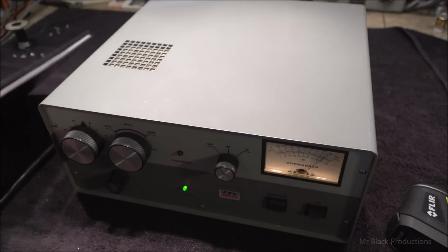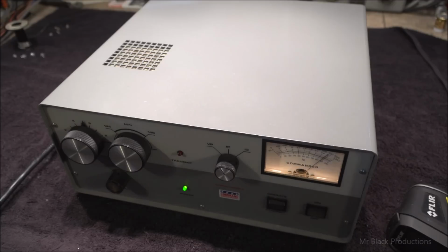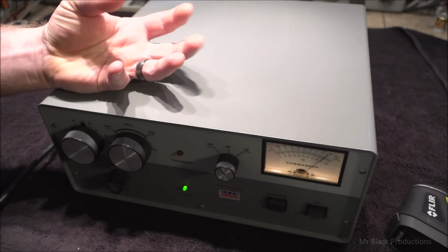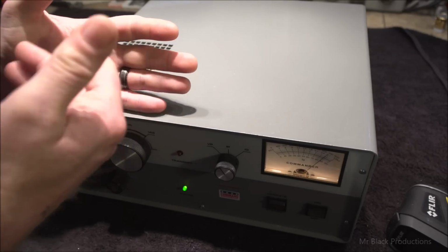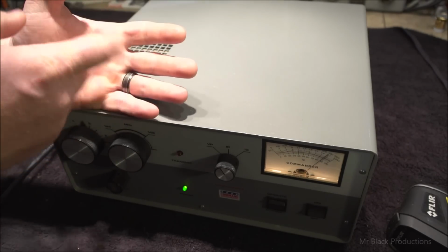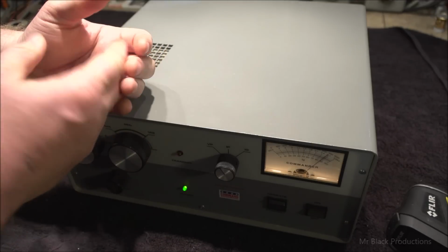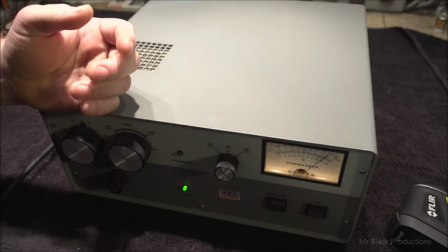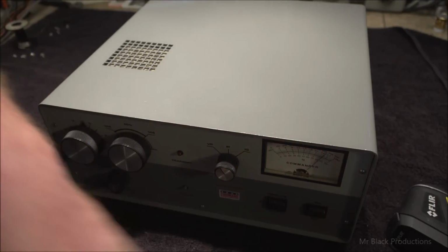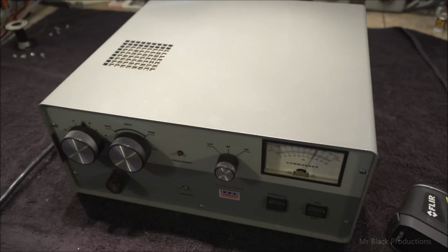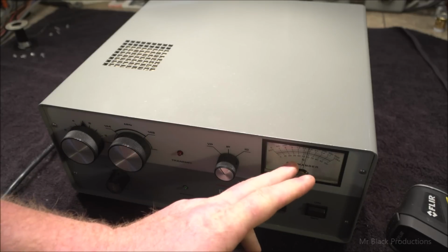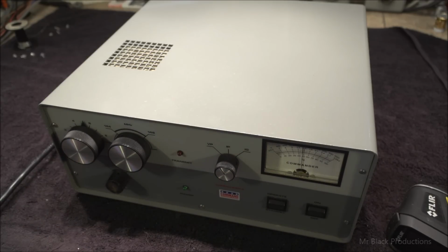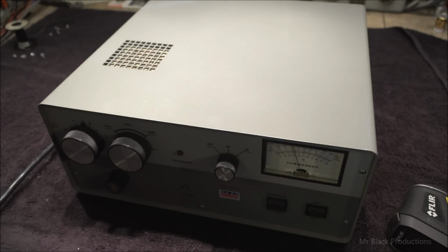So just in case, it's almost impossible, but one of the precautionary things that we do is we run the amp without any high voltage present on the anode. Let the filament sit there and bake, in case there's any chance of foreign gas molecules built up inside the tube. The tube sitting there building heat will take care of that naturally with the filament. So we're going to watch our high voltage bleed off. Now our high voltage is nowhere on our anode deck. Nowhere on the high voltage deck whatsoever.